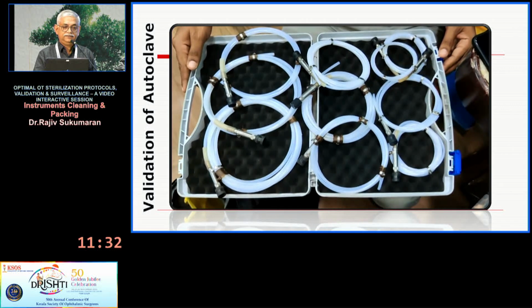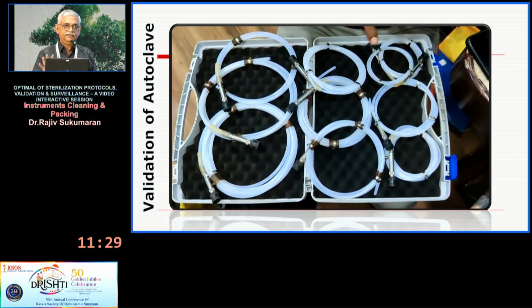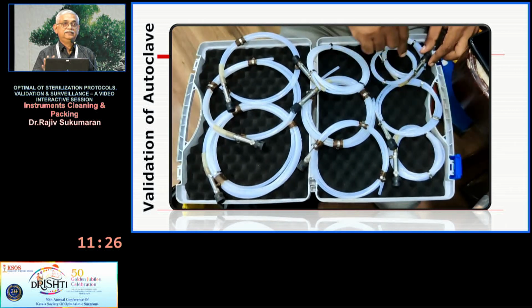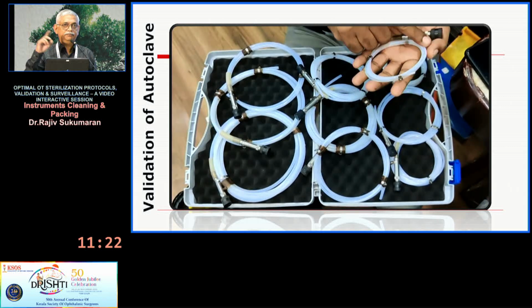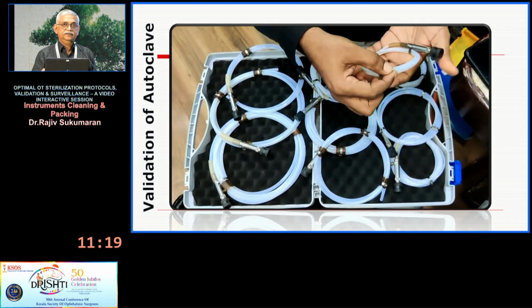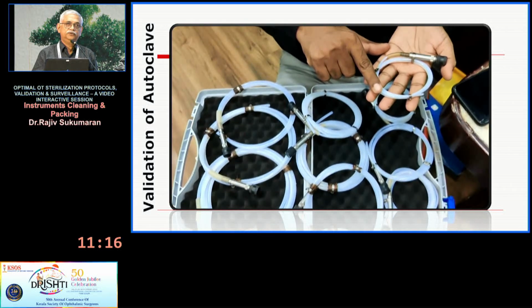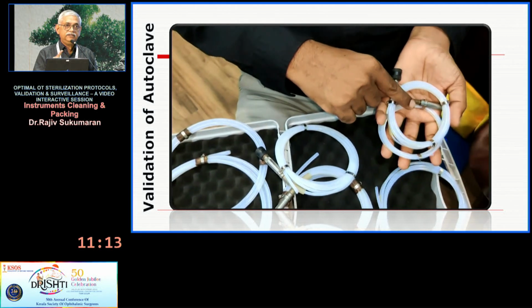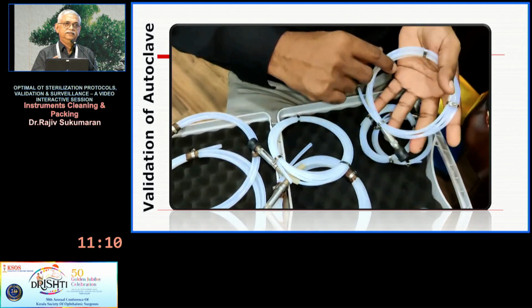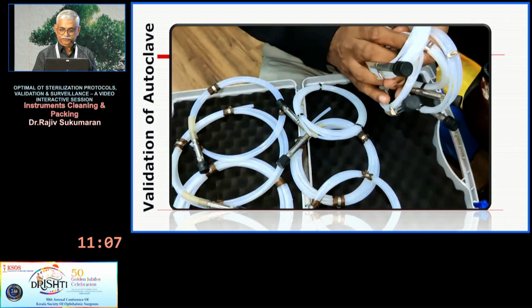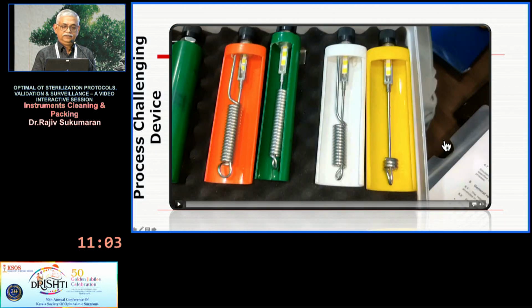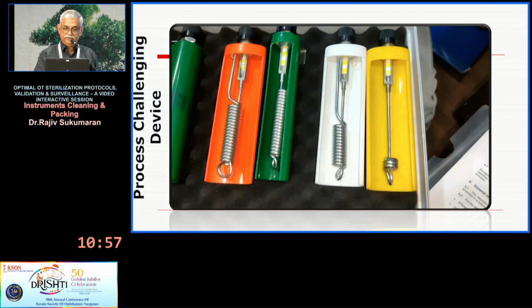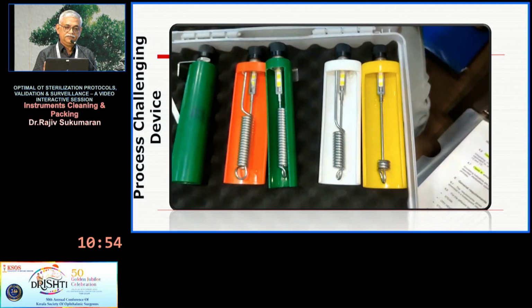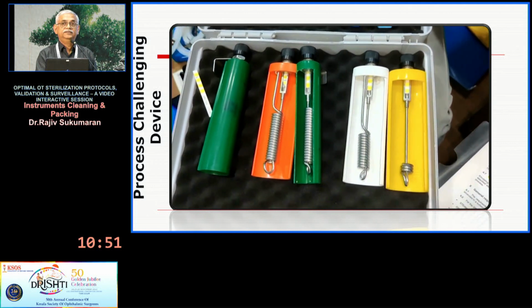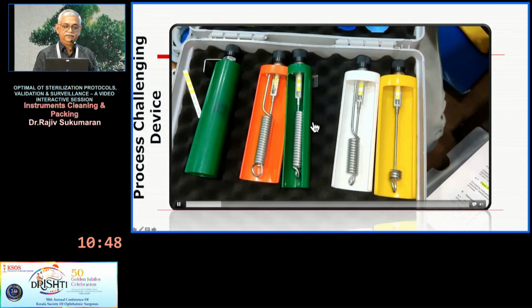And what I am showing here is a batch of 10 helix tubes. These tubes are used to standardize your autoclave. This is not done by you, but by the company when they come to install. These 10 helix tubes are of different sizes and calibers. All 10 have to pass the test if your autoclave is good. And this is called the process challenging device. This is cut open to show you how it looks inside. Actually, it will be fully covered. You will not be able to see these tubes and all like what you see in the green part. The open part is this one.